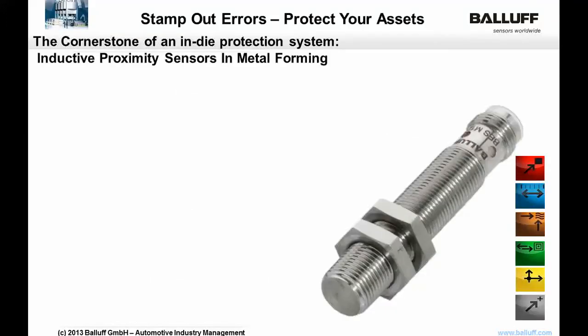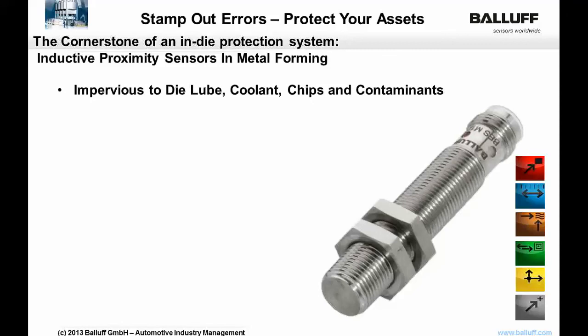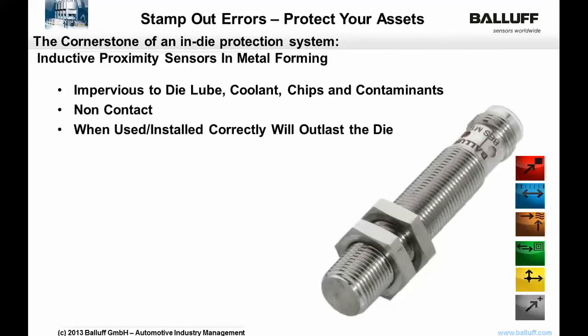The steel face inductive proximity sensor should be the workhorse product that you're offering to the press shop. These devices are fully stainless steel. They're impervious to external contaminants such as lube, coolant, chips, and the like. It's fully non-contact. And as mentioned earlier, when it's installed and utilized correctly, these devices will outlast the life of the tooling. They're designed for this environment.